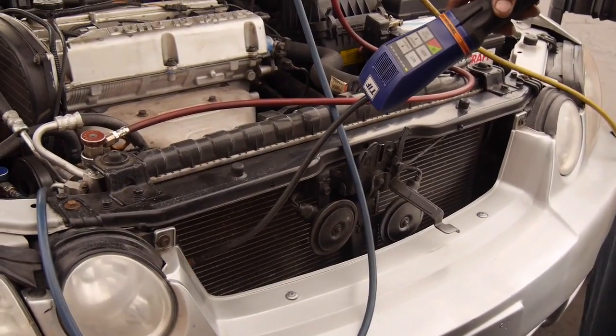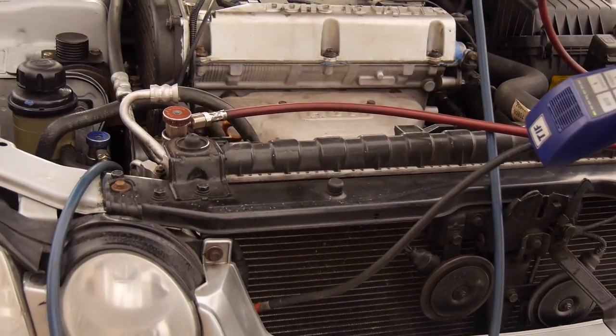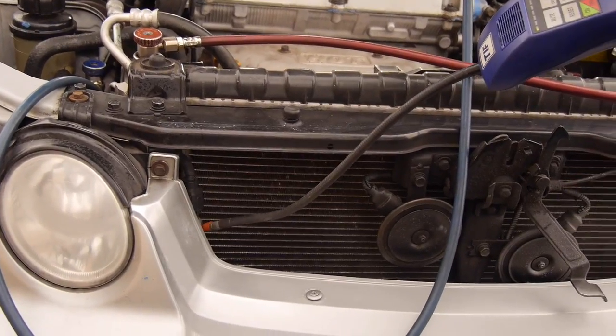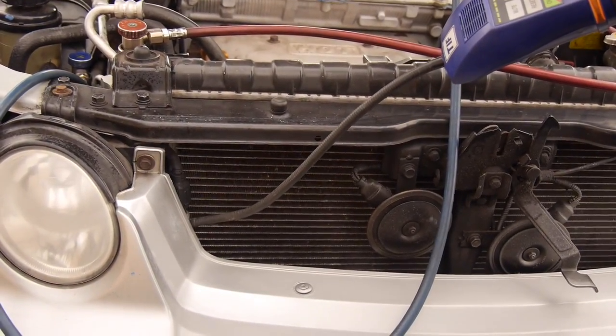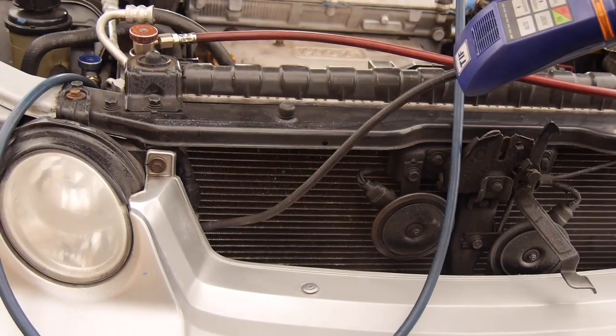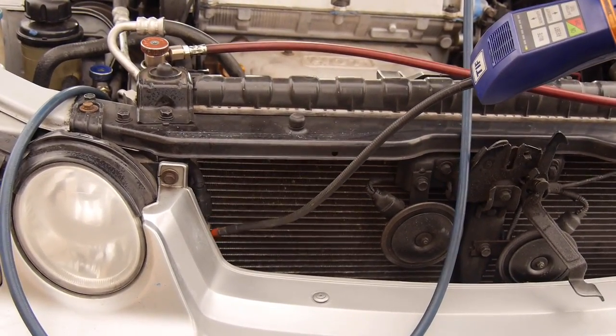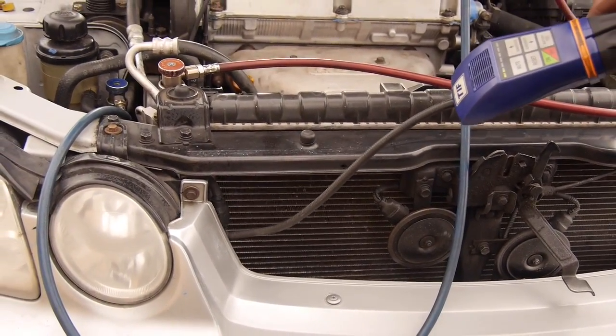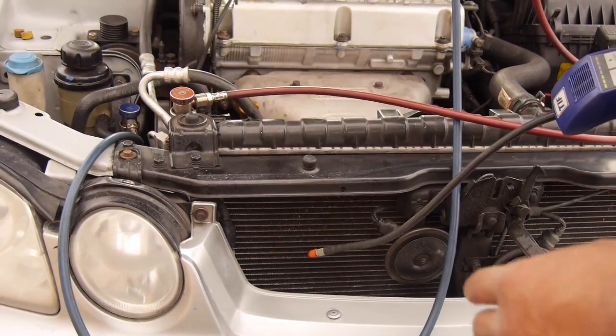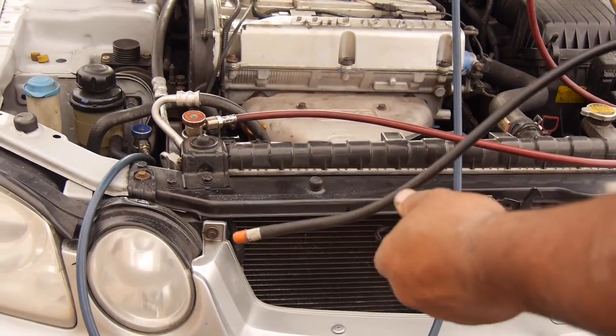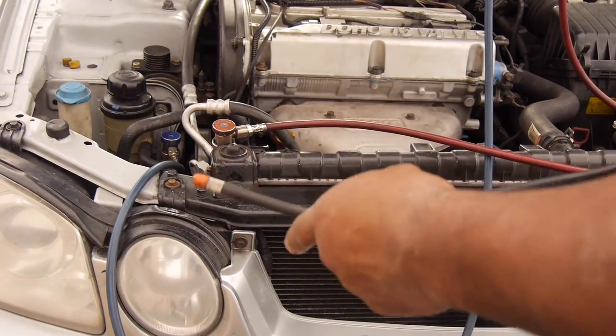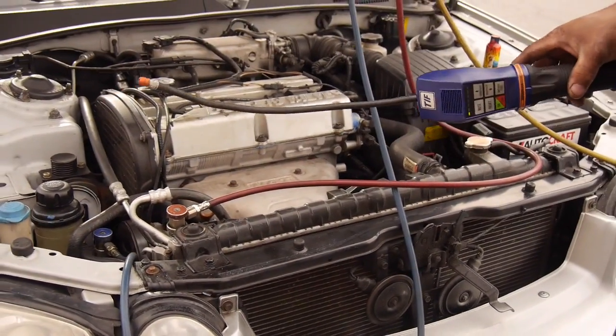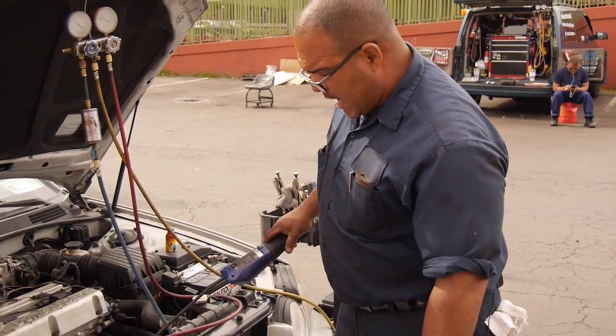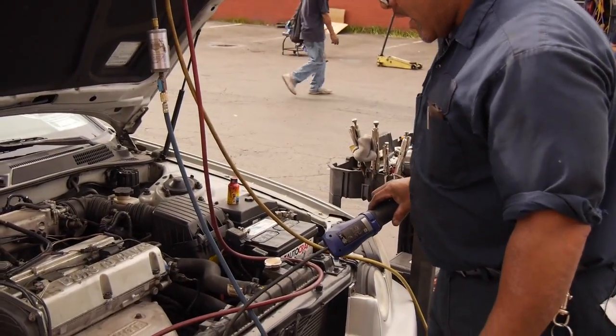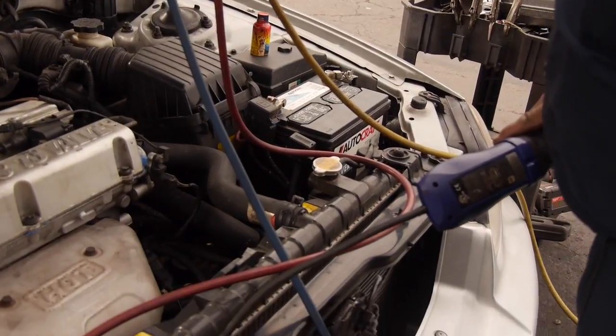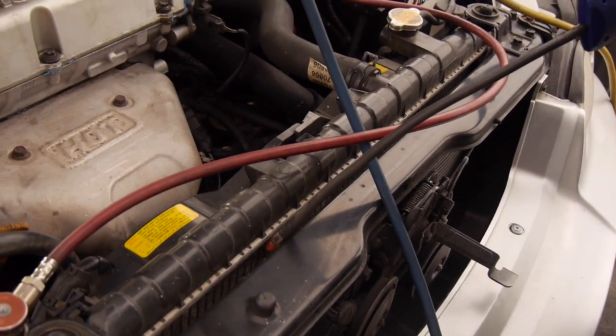You would check the filter dryer, which is this right here. That's the filter dryer and the cycling switch. You will come around that because that has an O-ring. It might be leaking. Like I said, you might get a beep here and there. And you want to thoroughly check the system out because you don't want the customer coming back with complaints. So you want to check it out thoroughly. I could go in between and check if there's room.